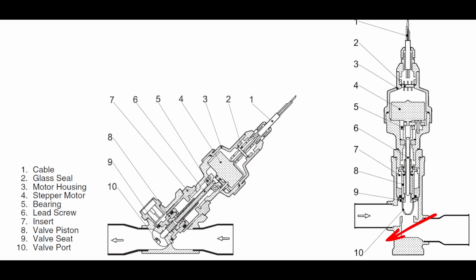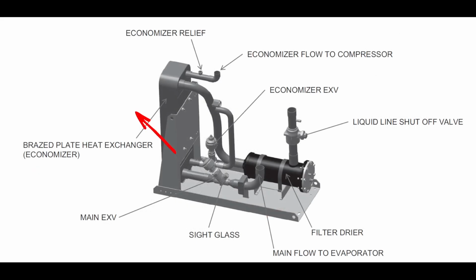And that's if they're using a body like this, or where we're in line on, say, our liquid line. You'll see this is very common on a lot of air-cooled applications. A lot of your air-cooleds are going to have a valve style like this, and you could have something that looks similar to this. So we've got two different valves, actually the two we were just referencing. This is how they would look in a field application. You've got both of them as straight pass-throughs. This one's at a slight angle just by its design. And this is your main valve for the evaporator.